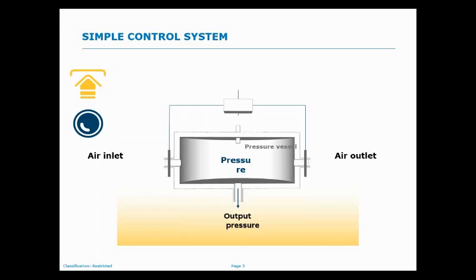See, the transmitter basically takes the physical signal, and you will have the necessary electronics like isolators and amplifiers, and it gives the output in the form of 4 to 20 milliamps or TCP/IP. Basically, in simple terms, the transmitter converts a physical signal into an electronic signal. When it comes to a PLC industry, the transmitter has to give it in industrial standard languages.